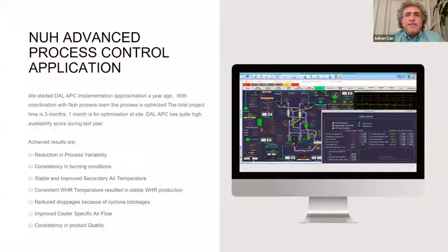And after achieving the successful performance under a separate contract, we installed the DAL APC Expert Advanced Process Control System. Also, with DAL APC, we have reached exciting performance improvements. The expert system regulates the kiln feed, kiln fuel, kiln speed, ID fan, cooler grates, and cooler fans. And the system has been running continuously for about a year now.